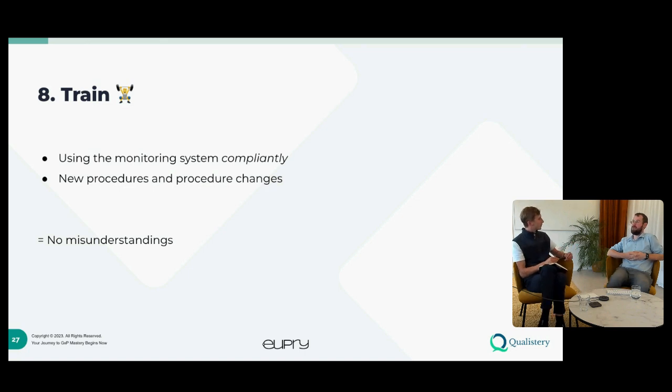And I would say that the good thing about having a Part 11 compliant system is always that if it's truly compliant, you have an audit trail. So it's always possible to go back and see which person did what. But of course, if you fall into the pitfall of having shared users, for example, it's really not possible to see which users did what changes. So that's often one of the pitfalls as well.